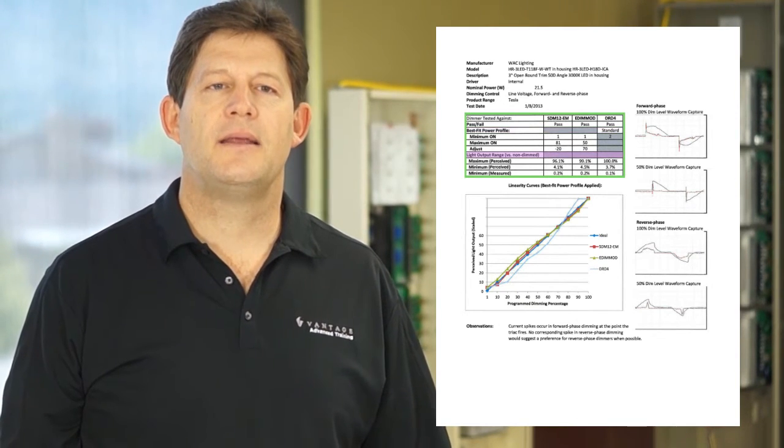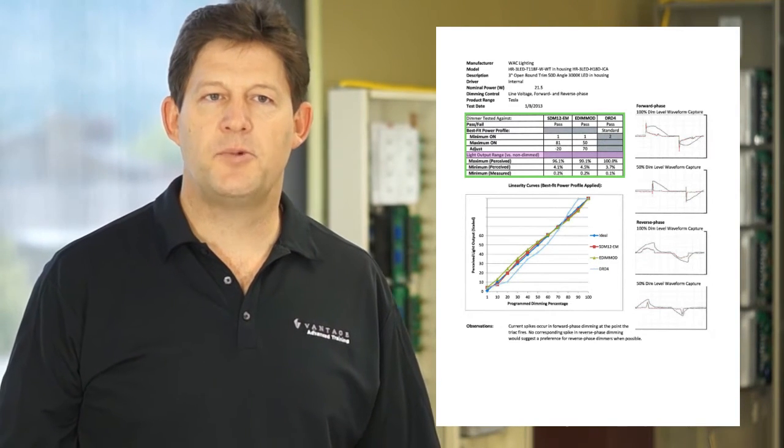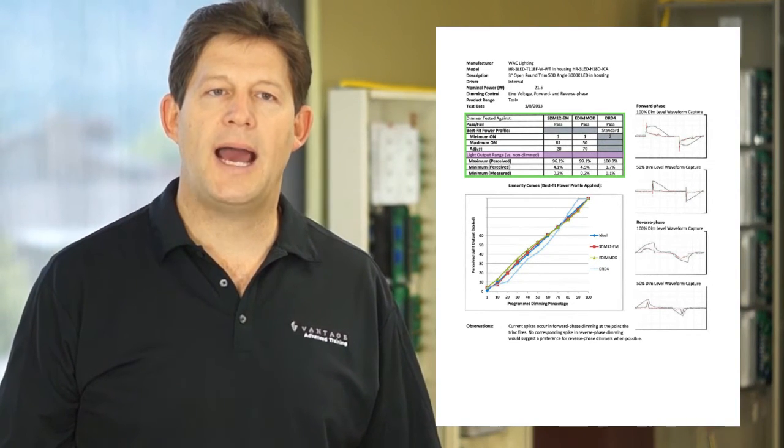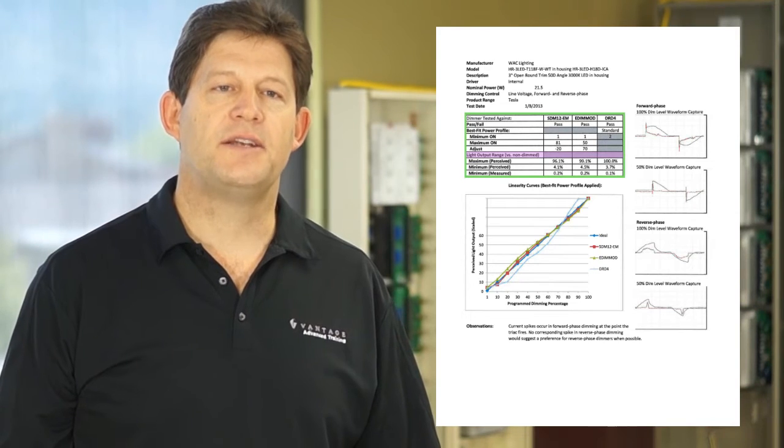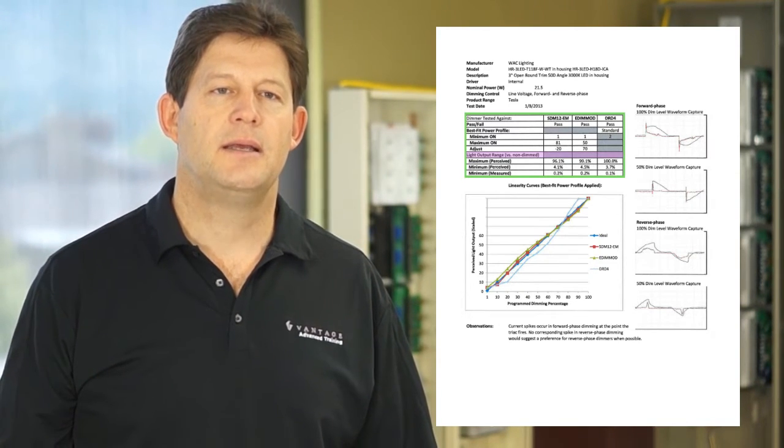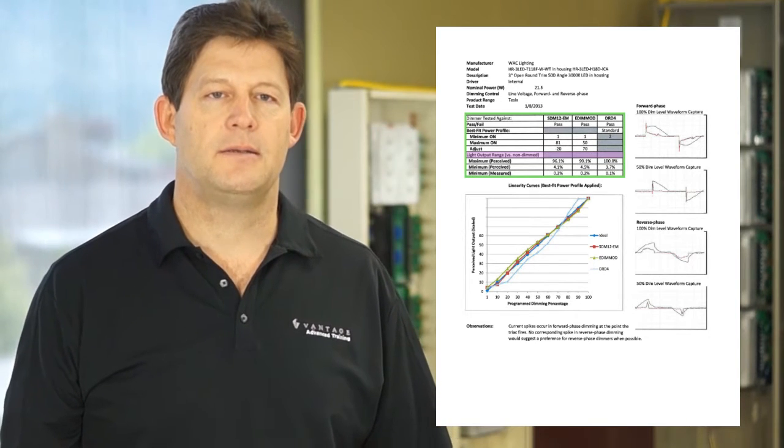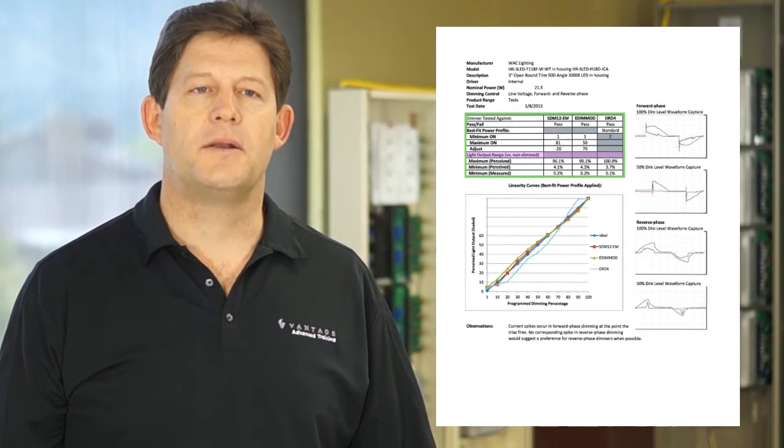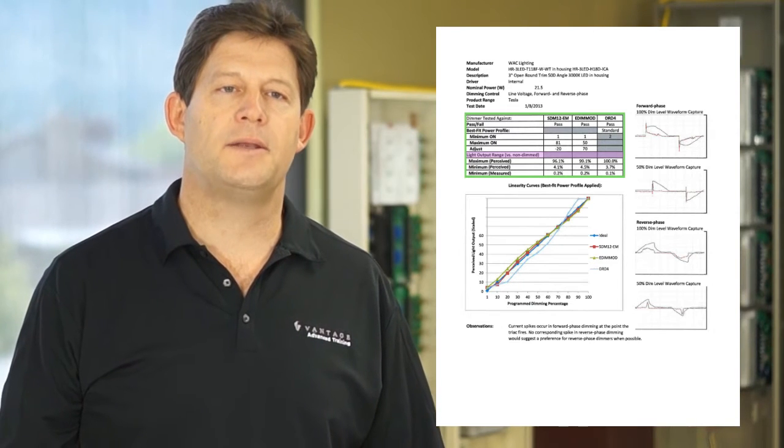Finally we display the maximum and minimum intensities. Because we apply a maximum on or high end trim to native Vantage dimmers, we may see a slight reduction in maximum intensity, never less than 95%. The DRD4 maximum will always be 100% because there is no high end trim.